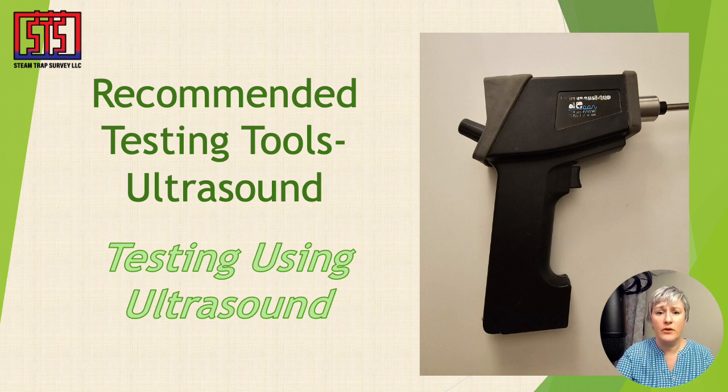If the sound heard is a continuous rushing sound, it is most likely stuck open and wasting steam.